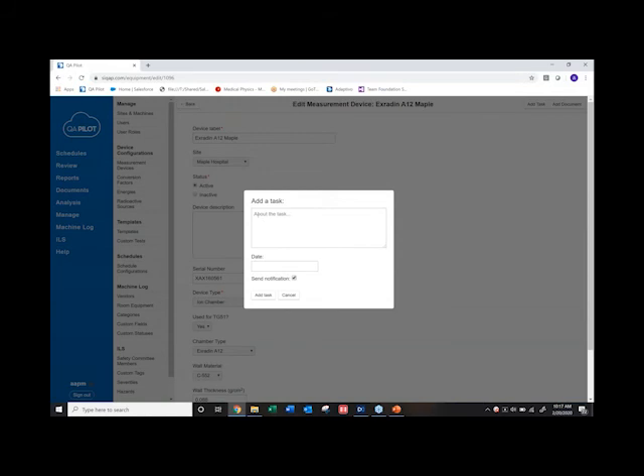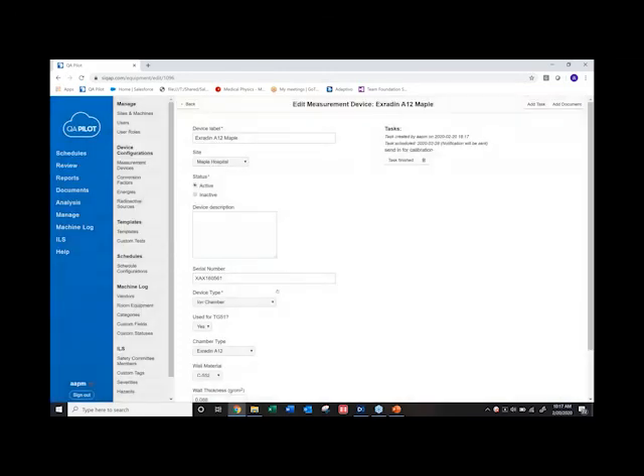You can add a task to say when it needs to be recalibrated. You just get it back, you know what your 2-year date is, you can enter the date here, assign the date for it to show up, for you to be notified. And yes, we have send notification on here, so you can say send in for recal, we can just do that, send in for calibration, give it a date, say it's at the end of the month, and we can add that task. And therefore you'll receive a notification when it's time for you to send in your device. Nice way to help you organize and be alerted to those things so they don't fall through the cracks.